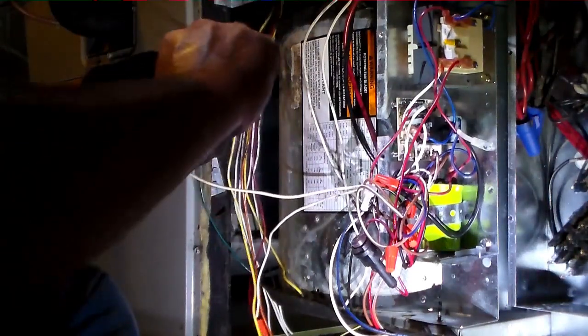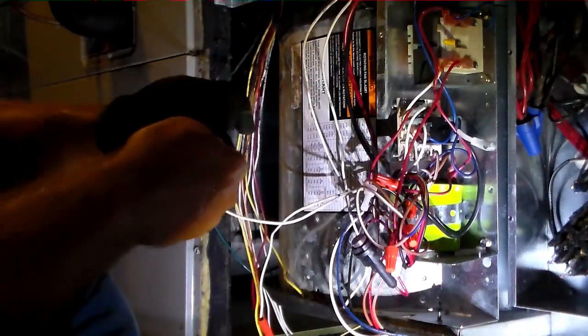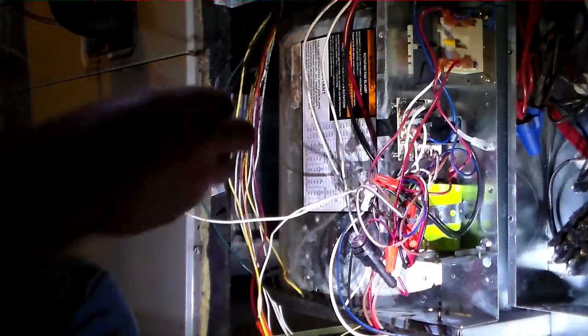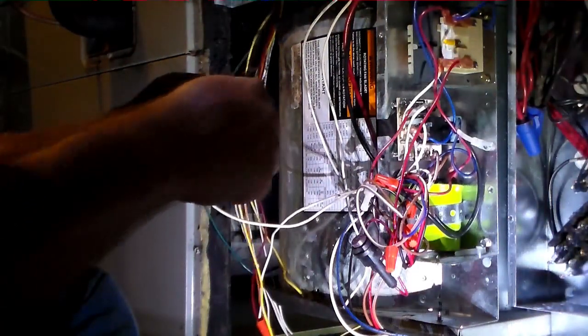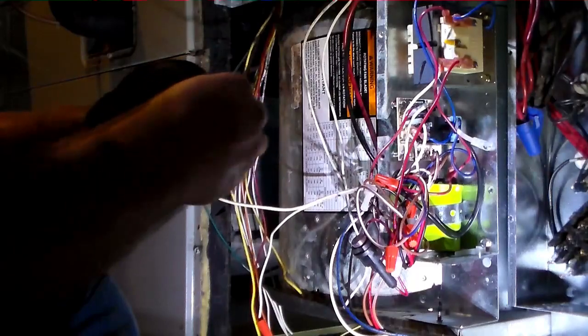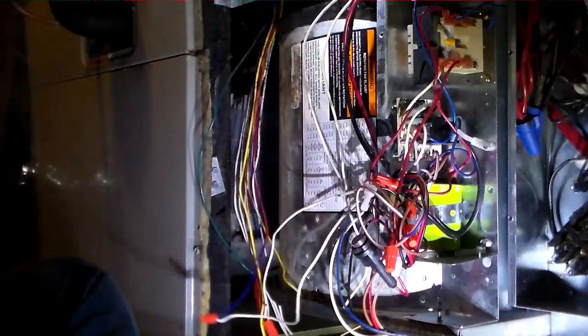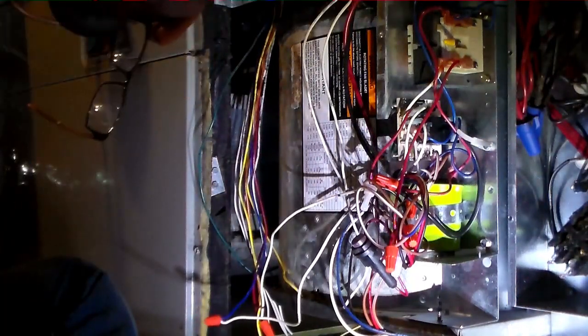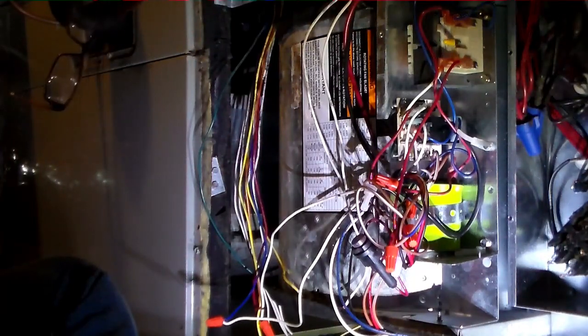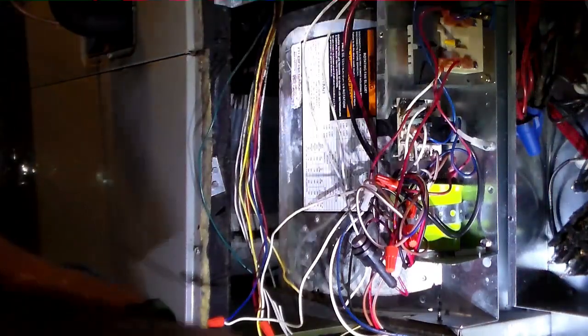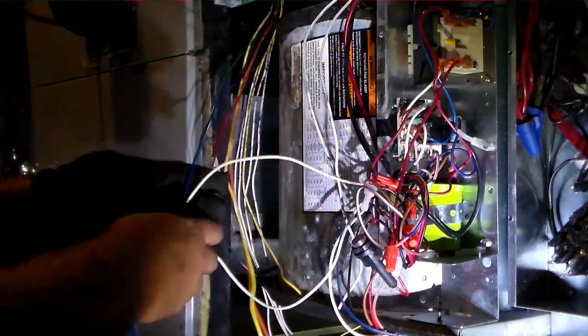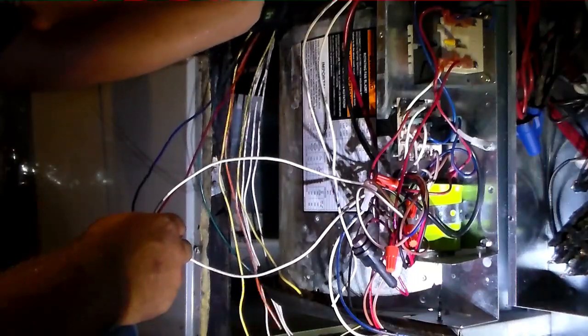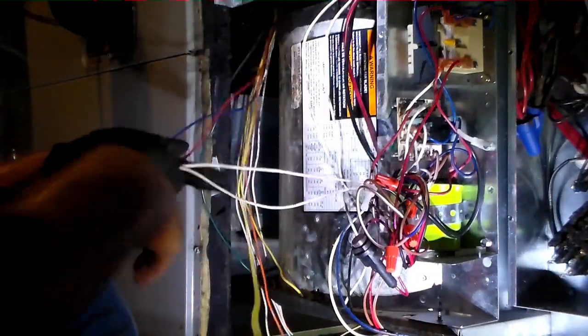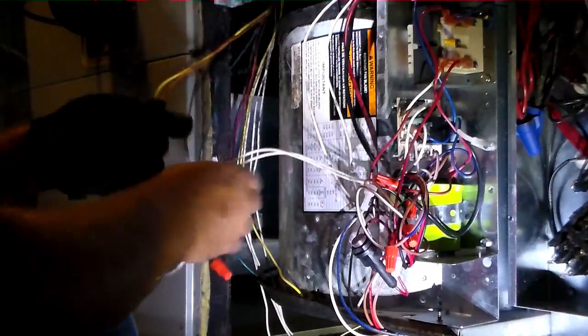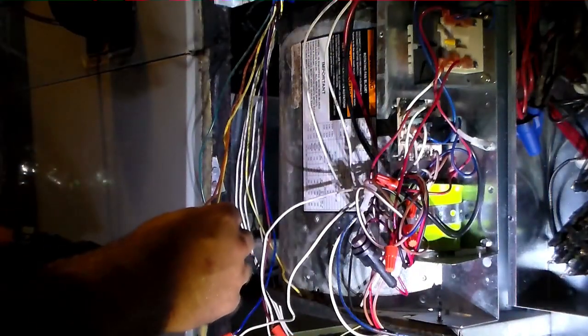The reason why you keep the PSC motor instead of going back with a variable speed: one, this guy is selling this house, and two, this would have been the third variable speed motor gone into this equipment. Maybe because of the zone system, recycling very cold air. There is a minimum. There's an air temperature sensor up here. I don't know if you can see it, but it senses air temperature. Won't let it go below a certain amount, but still it stays a little colder in there than it normally would.